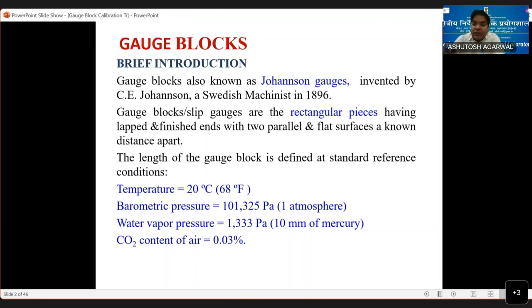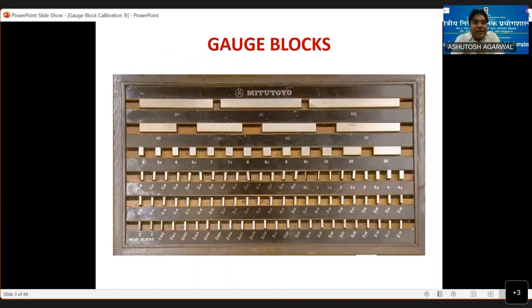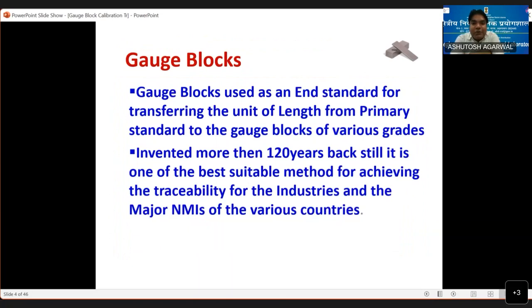So gauge blocks are nothing but rectangular pieces, but it's not only rectangular. I will show you they are circular also. This is a typical gauge block set we have in most of our systems. So these are the gauge blocks. What are gauge blocks? Gauge blocks are used as an end standard for transferring the unit of length from the primary standard to the gauge blocks of various grades. I will show you 0 grade, K grade, 1 grade, 2 grade.